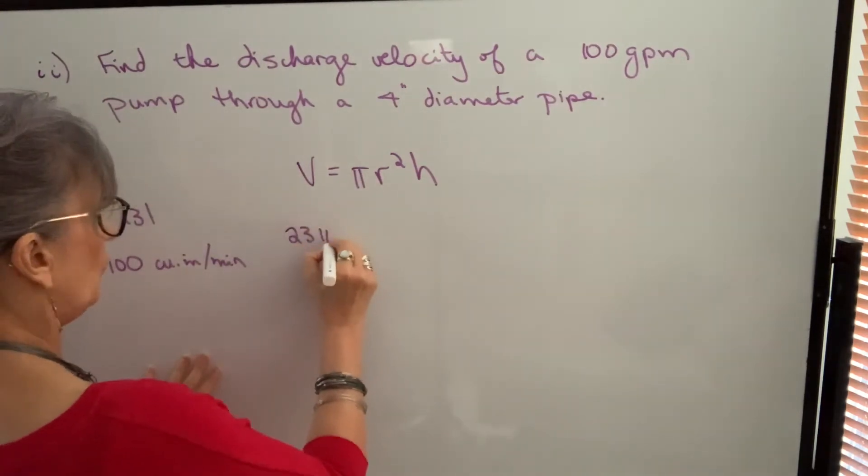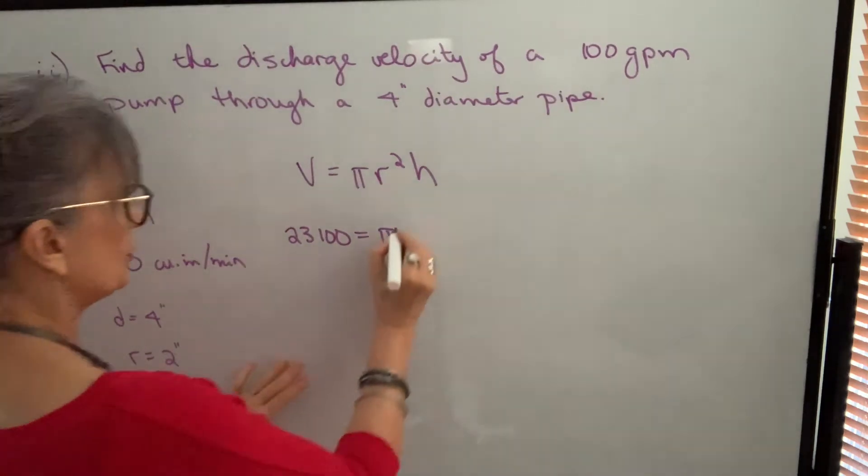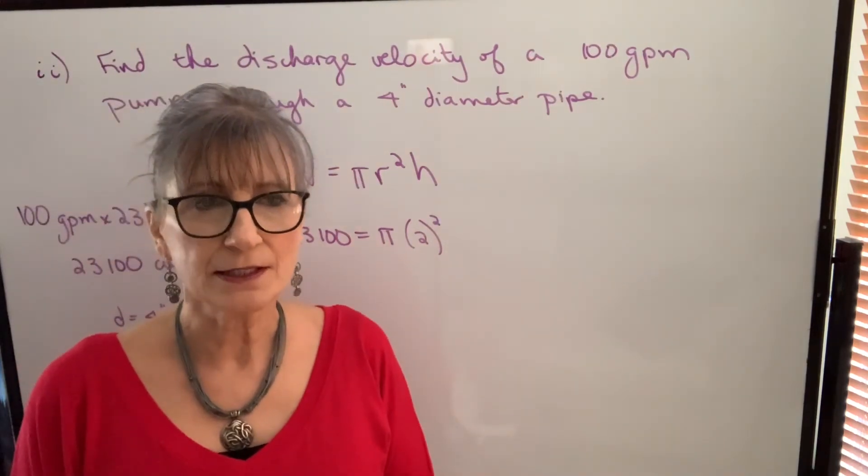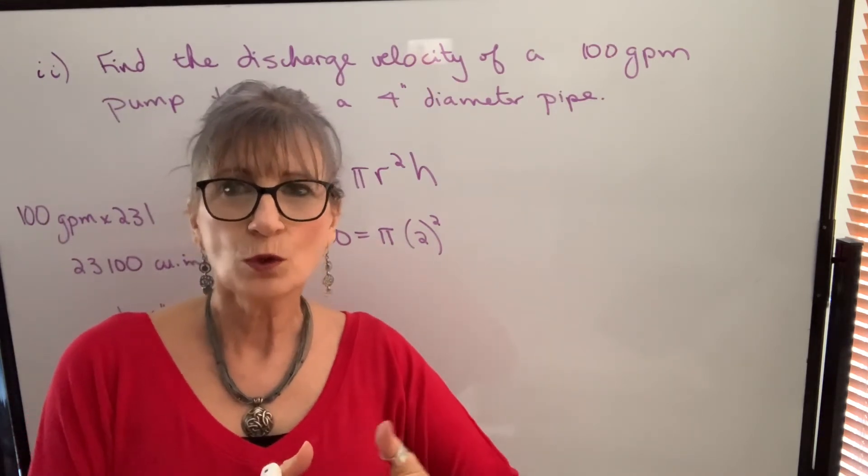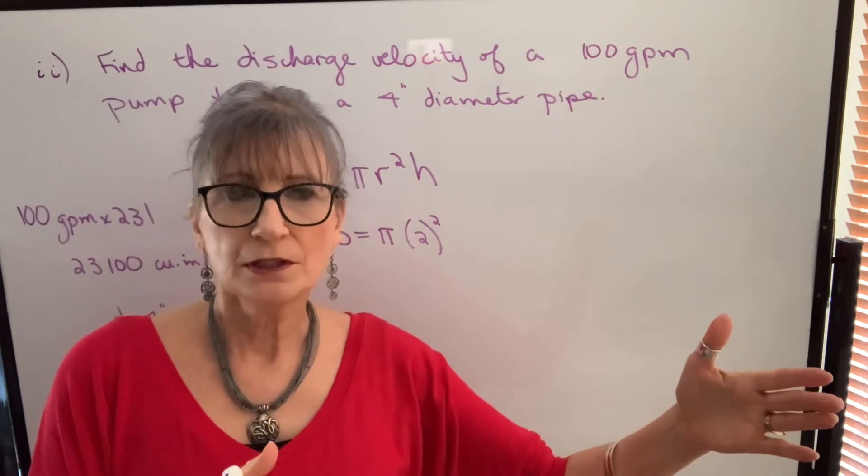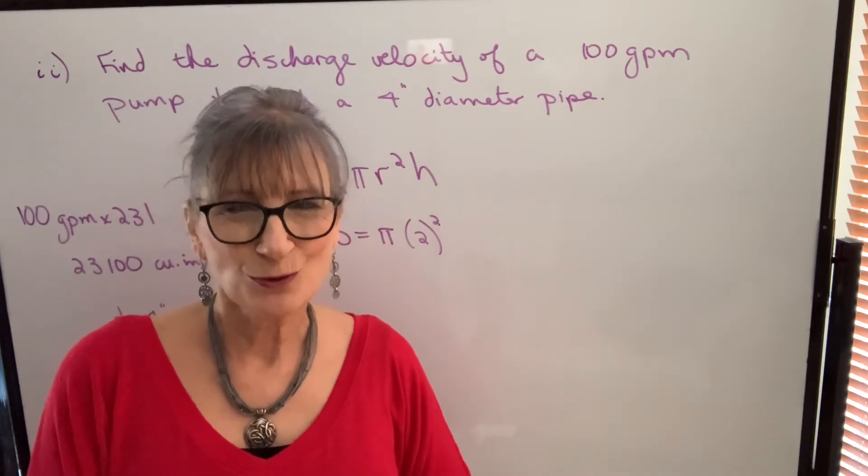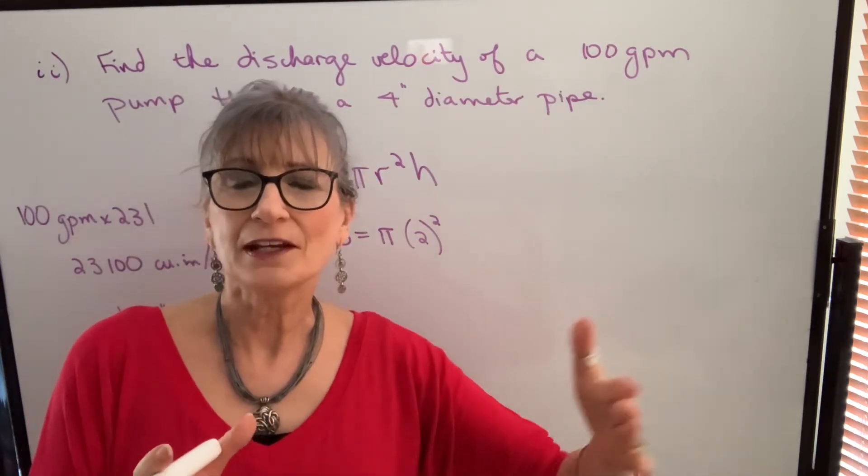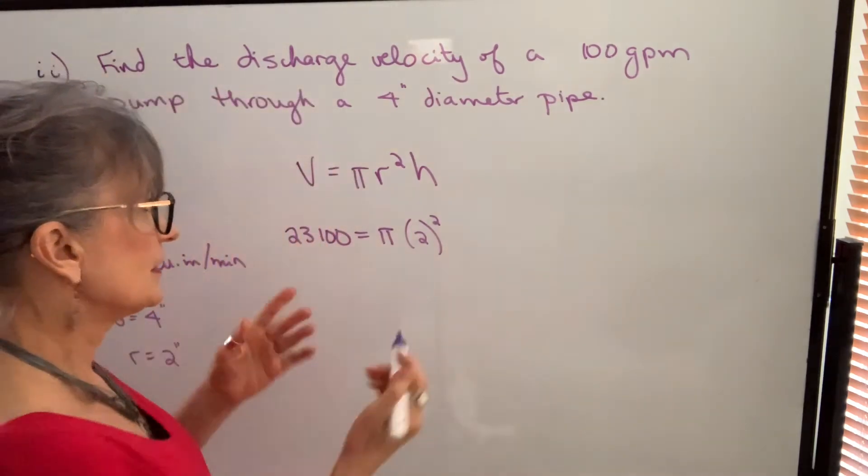So that's the volume of fluid that's flowing through that pipe in one minute of operation. So we're going to put that in for volume. 23,100 will equal pi times, the diameter is 4 inches, which we want to be in inches. Our radius is half of that, so our radius is 2 inches. So we put 2 in for radius. And we're finding the discharge velocity. We're not really finding the height. But in order to find the discharge velocity, we think of it as being height. What total length would that pipe need to be to hold the fluid that's discharged in a minute of operation of that pump? So we think of it as height, even though it truly isn't really a height of the pipe. But it's the distance that that fluid will travel, which would be the same as what the length or the height of the pipe would have to be to hold the discharge in a minute of operation.